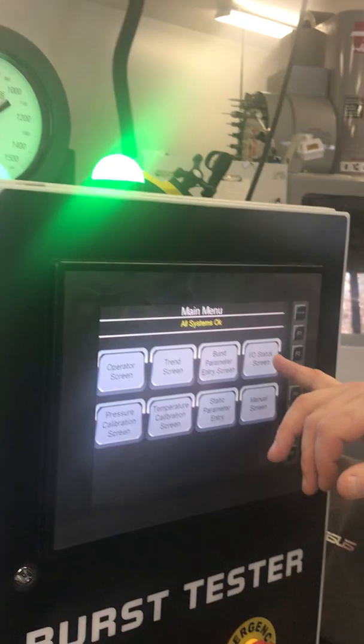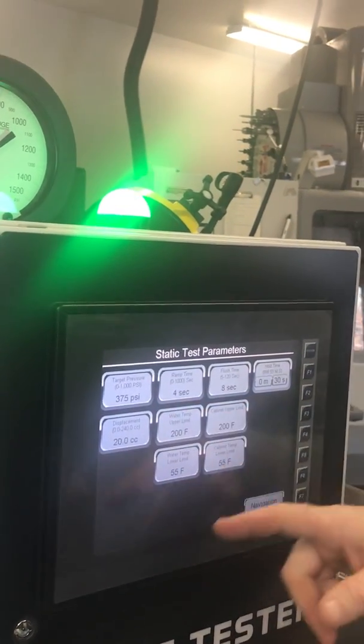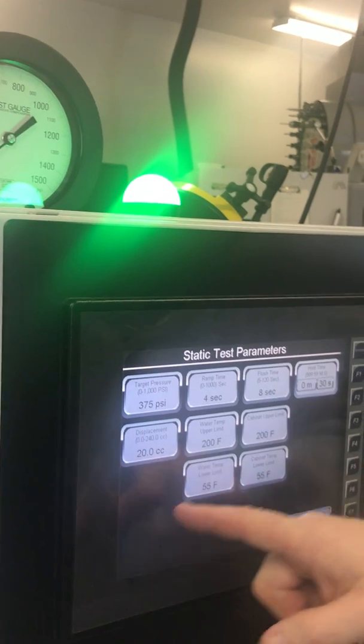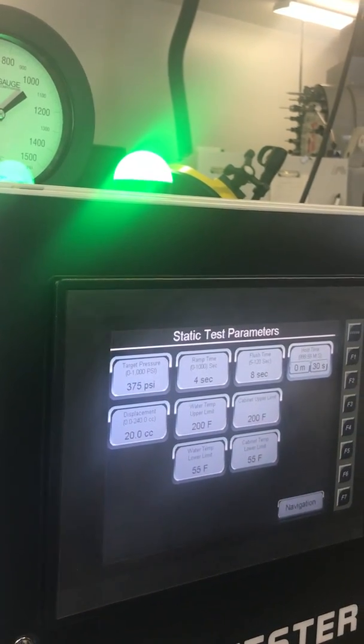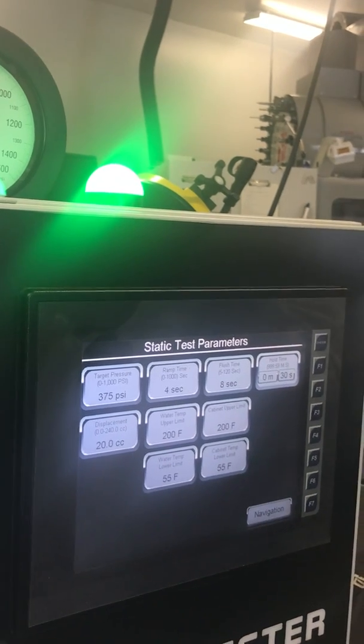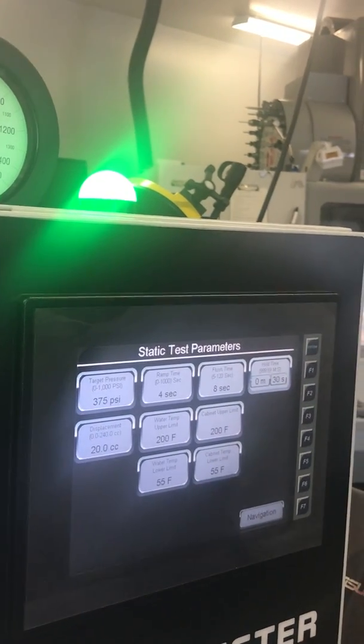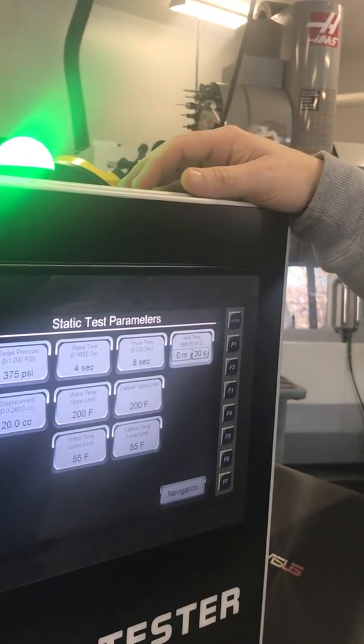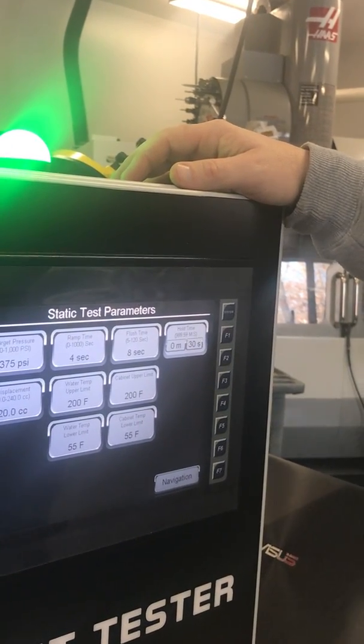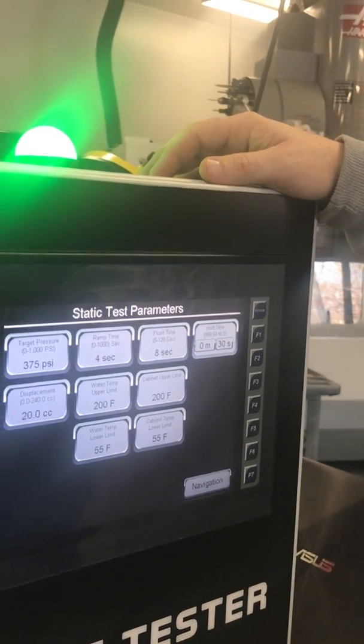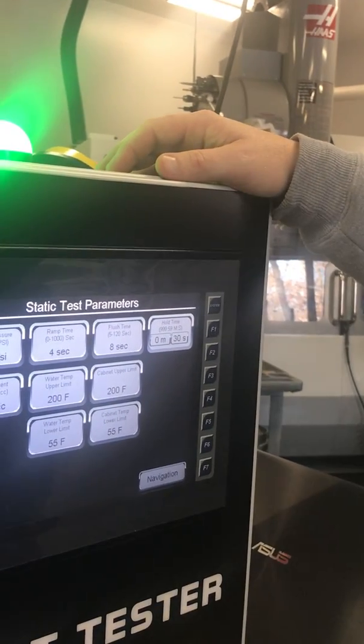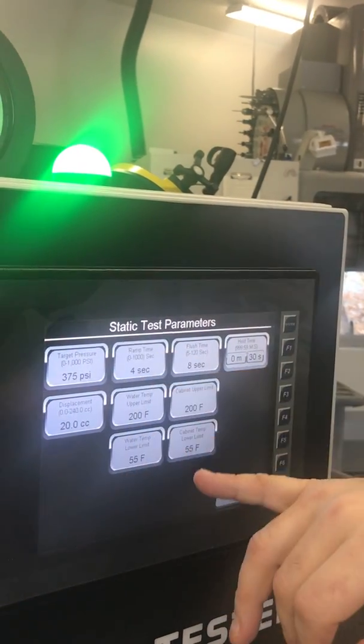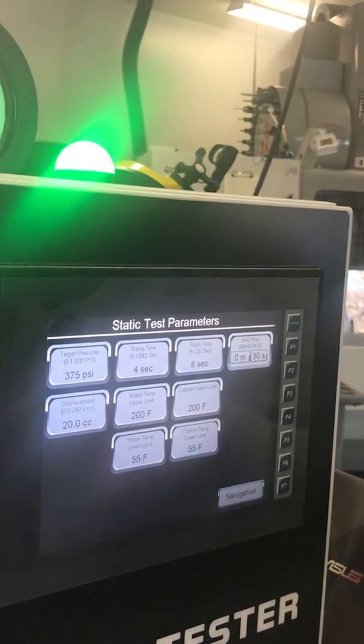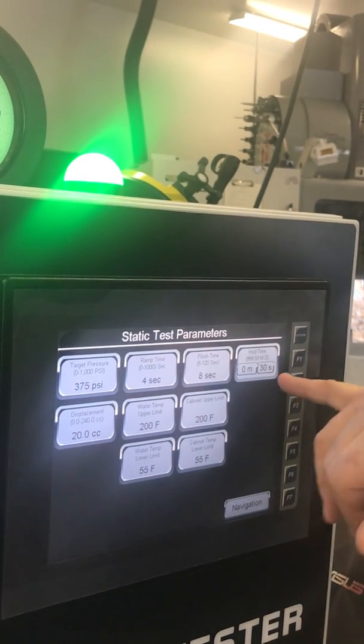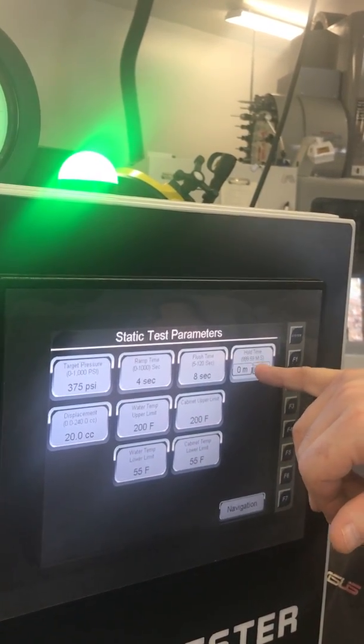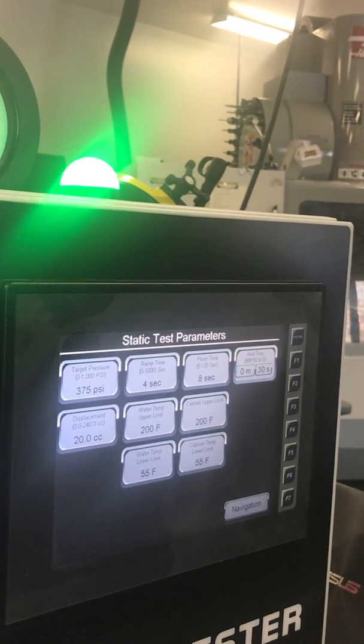Let's go into the static pressure one. It's almost identical to burst, except we do not have this one here, which was that once you exceeded X PSI, we'd pass it even if it fails later. You said we have to clear 500, but bring it up to 1,000. So there are two numbers, the 500 and the 1,000, but you can adjust them. In static, you don't have the 500 number. It's like: target pressure 375, get there in 4 seconds, flush for 8 before we start, and hold for 30 seconds. But you can go 999 minutes and 59 seconds and just hold it there.